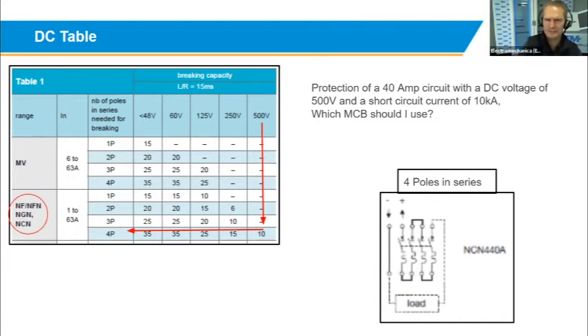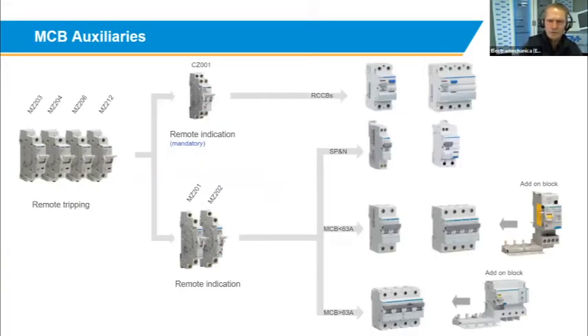So these products are rated DC. You can just have a look at the table at the back to see which one you can use. Then just on the product offering, on the miniature circuit breakers, you can add a lot of accessories onto the product to give you different scenarios. So if you want to do remote tripping, you want to put a shunt trip onto the product, UVT, and even an over and under voltage tripping device. You can add that to a miniature circuit breaker. I'll show you just now how to do that.